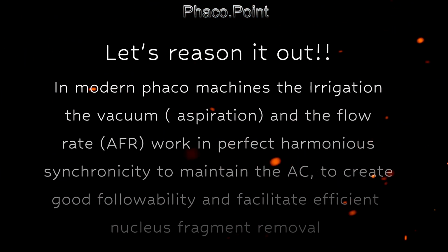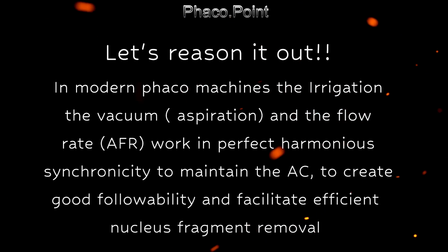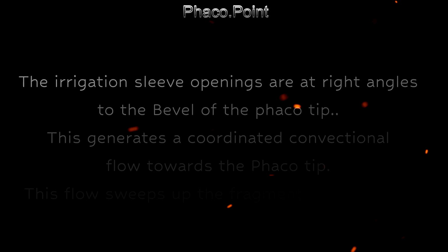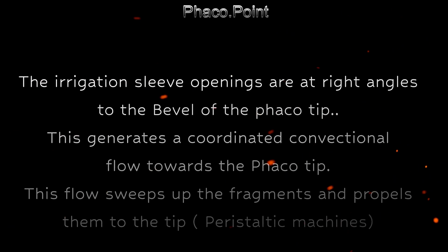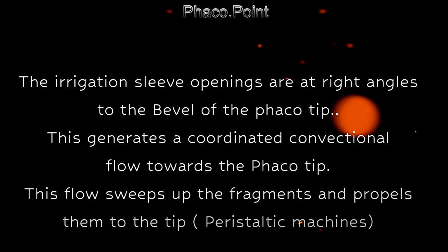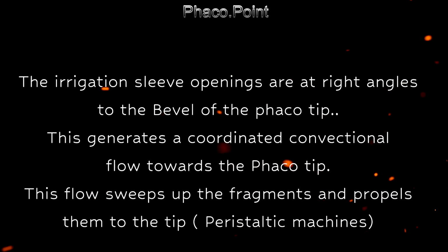In modern Phaco machines, the irrigation, the vacuum and the flow work in perfect harmonious synchronicity to maintain the AC, to create good followability and facilitate efficient nucleus fragment removal. The irrigation sleeve openings are at right angles to the bevel of the Phaco tip. This generates a coordinated convectional flow towards the Phaco tip. The flow sweeps up the fragments and propels them to the Phaco tip. This happens in peristaltic machines. In Venturi machines, it's the vacuum that generates the flow, but the mechanism is more or less the same.